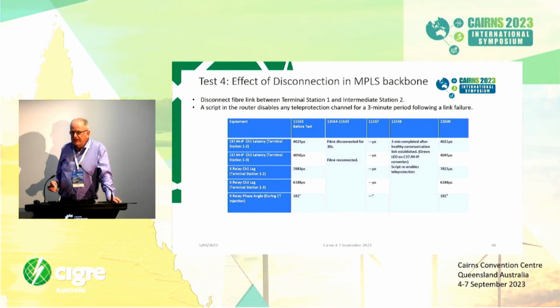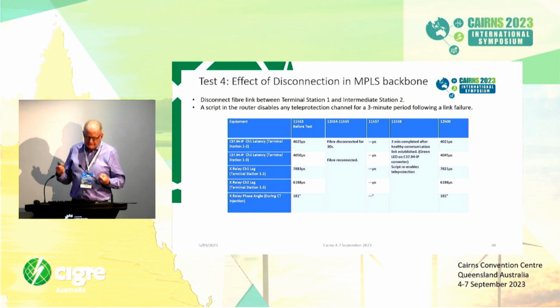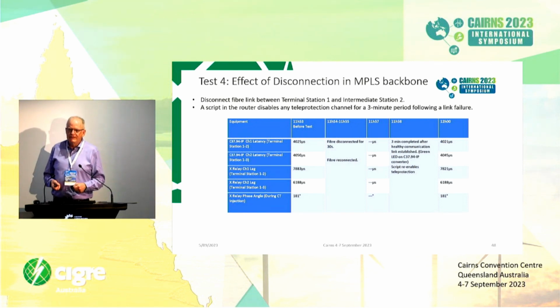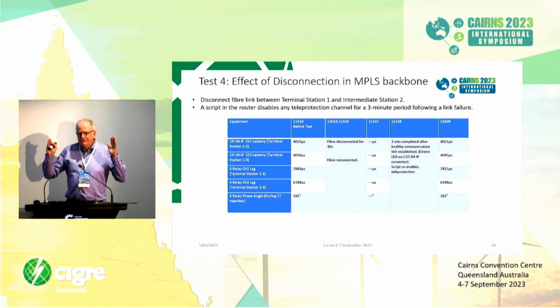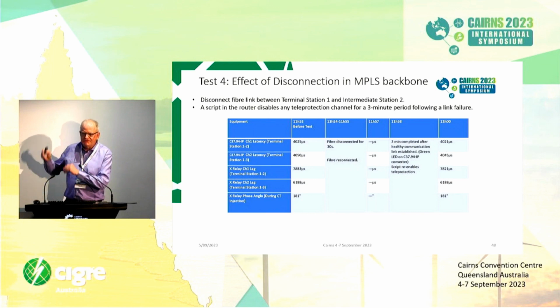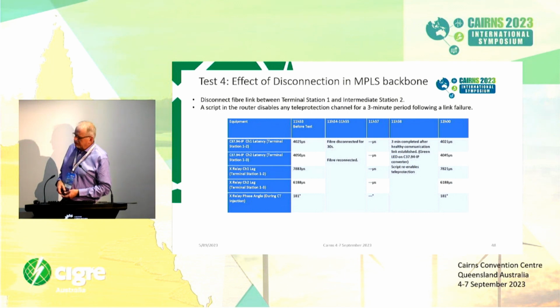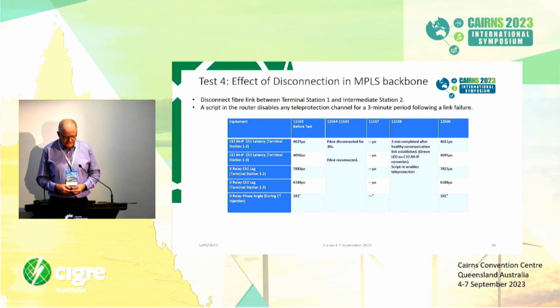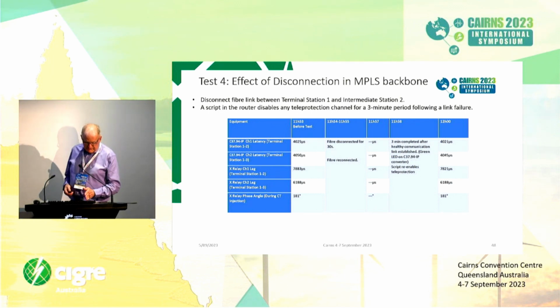So when we get a failure of the communications backbone, the network will hard fail for a period of 3 minutes, just to stop that flapping effect, so we don't get communications coming up for a few seconds or so, going down, etc., because we figure that might cause some problems for the protection relays themselves. But once again, very, very stable here.